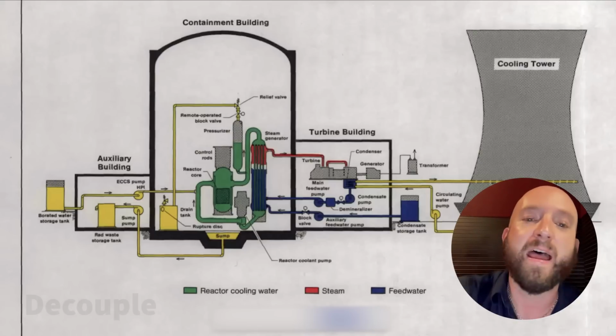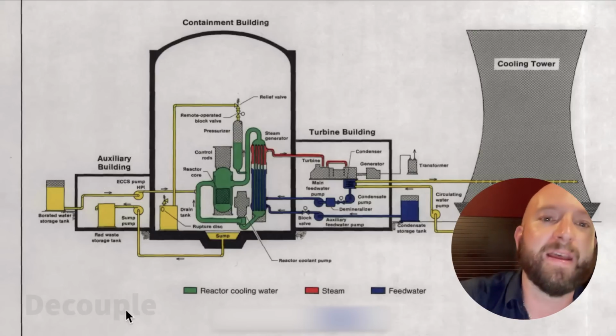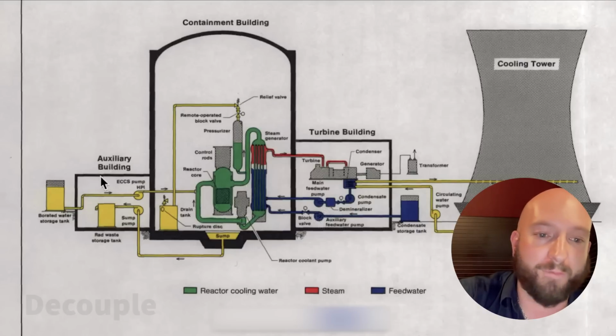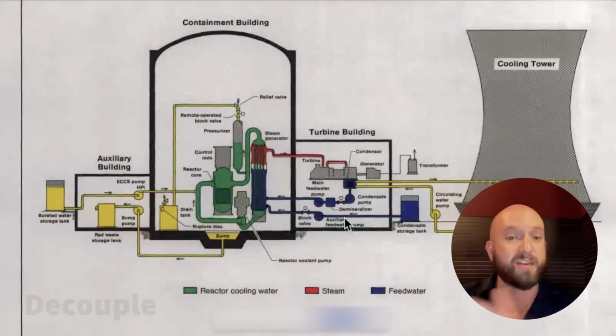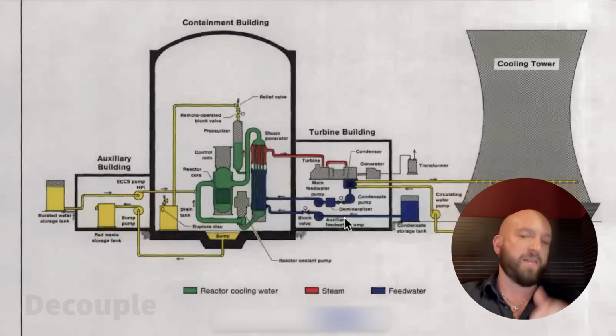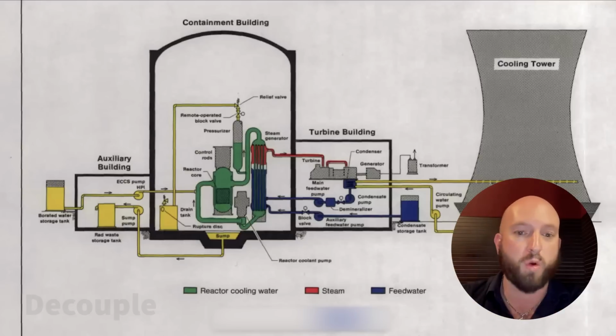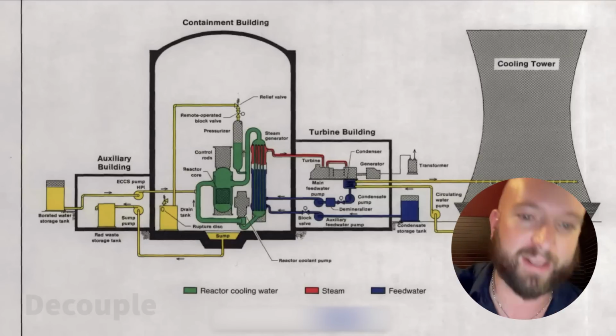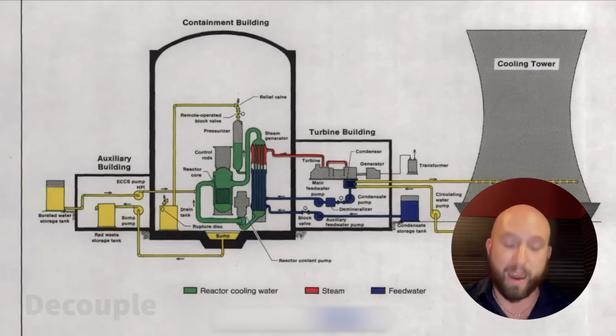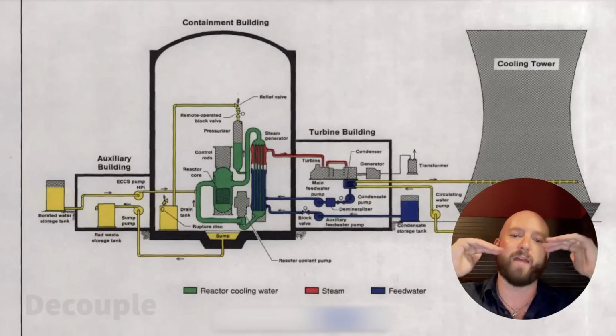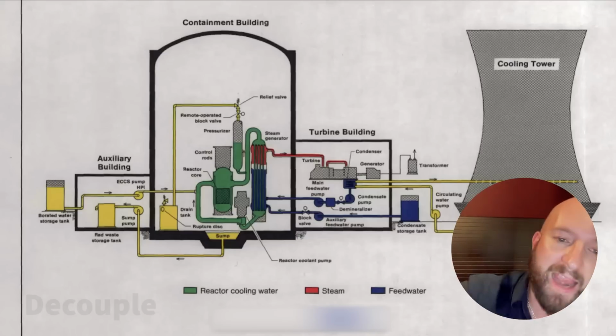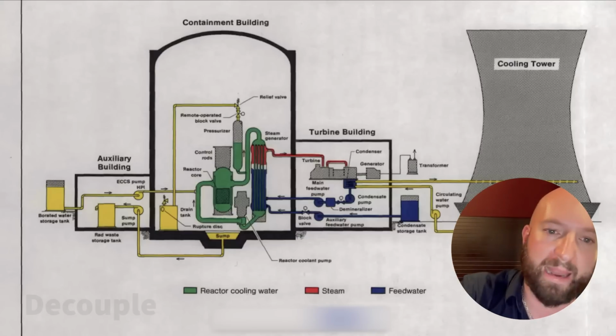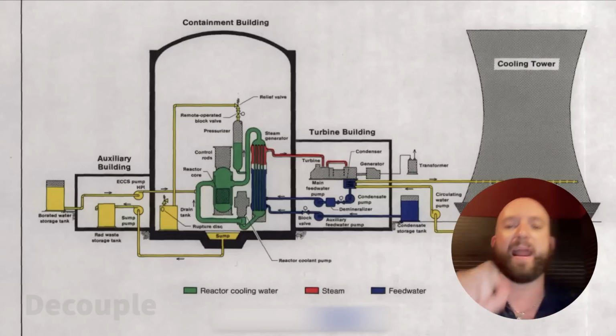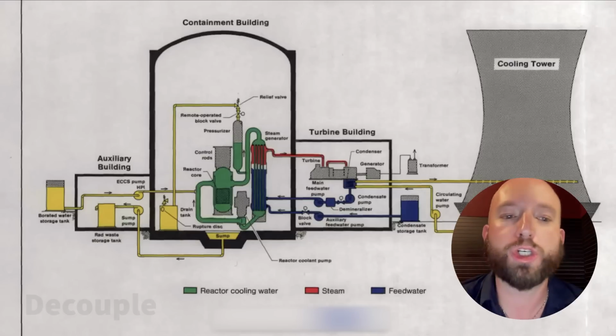In fact, there are even other things that the plant did automatically to prepare for an accident that weren't necessary. For example, when the emergency core cooling system spun up, the emergency diesel generators automatically kicked in, saying, hey, the plant's in an abnormal configuration, maybe there's a storm or an earthquake. Let's get our emergency diesels turned on to prepare for a loss of power, which never happened here. But it just gives you an idea of the level of engineering rigor that went into designing these safety systems to automatically put the plant into a stable configuration. The one thing they hadn't anticipated was that the operators would shut down that emergency core cooling system. Enter the human factors.